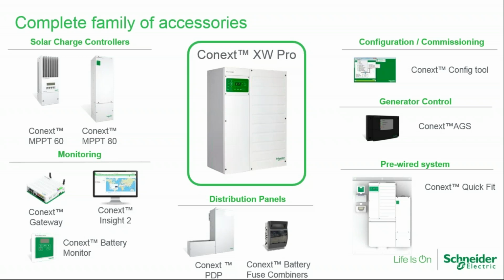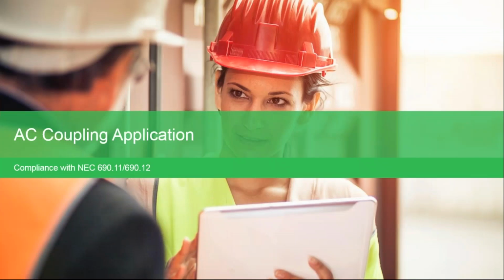If you notice in the lower right-hand corner, there's a pre-wired system, which we call Conext Quick Fit. And there are 7 versions of that implement different charge controllers and different inverters. And then there's one that basically does not have a charge controller and is set up for AC coupling. And so you can basically just get a pre-wired system, hook it up to the wall, connect it into the sub panel, and with your PV inverters also connected to that sub panel, you have a quick install AC coupled system. And that leads us to AC coupled application. Compliant with NEC 690.11 and 690.12, which are arc fault and rapid shutdown.